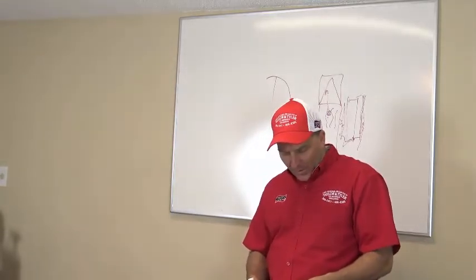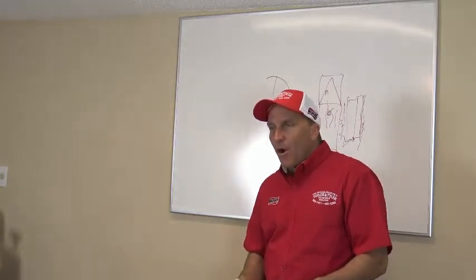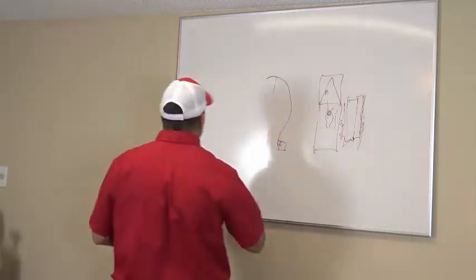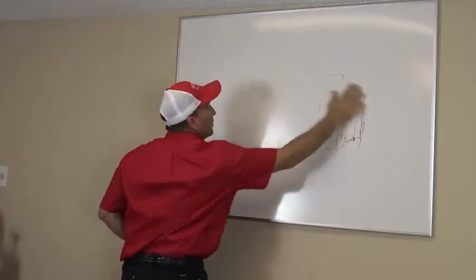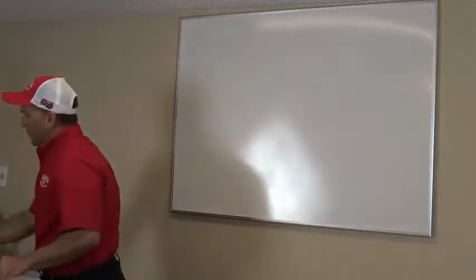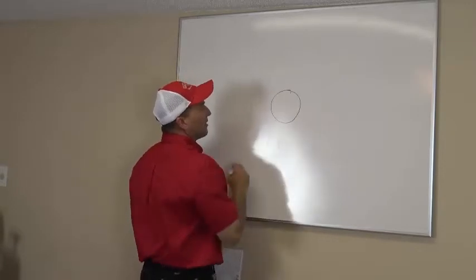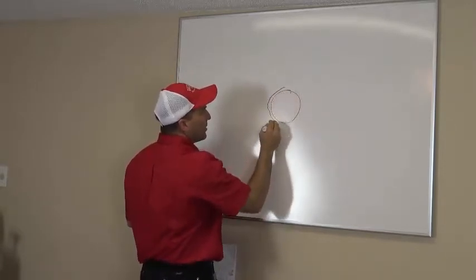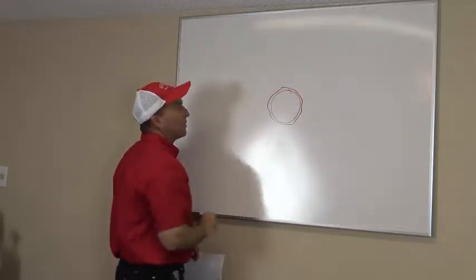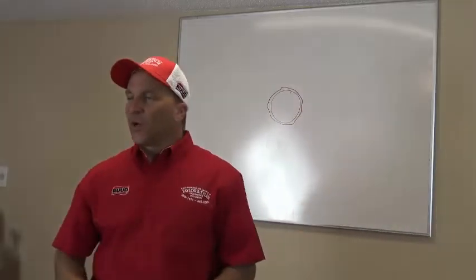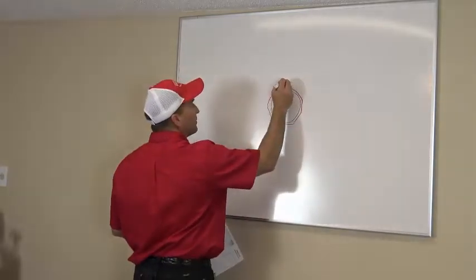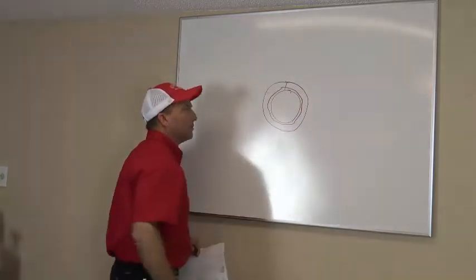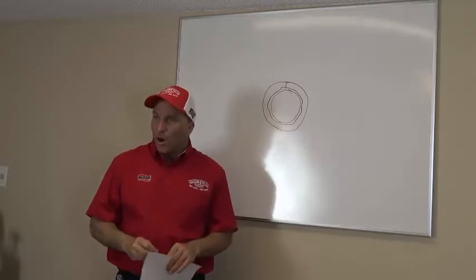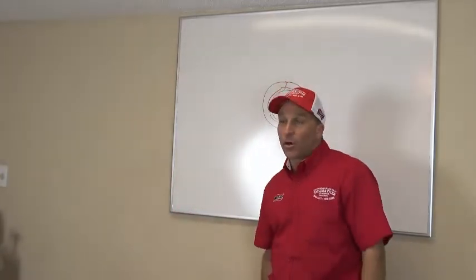All right, I want to know the duct insulation. If you got hard pipe duct, watch how this works, guys. Okay? Hard pipe duct. What happens to the insulation through the years, guys? There's the inside of it, right? Here is the insulation around your ductwork, literally, right? A quarter of an inch. Okay? When it was originally installed, it was R4 value insulation on that duct, which was 1 inch. Okay? That was original. There it is today. R4 is 1 inch. What's a quarter inch? R1. Okay, R2, max.